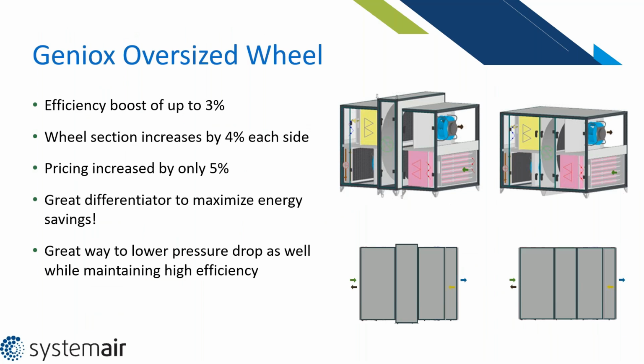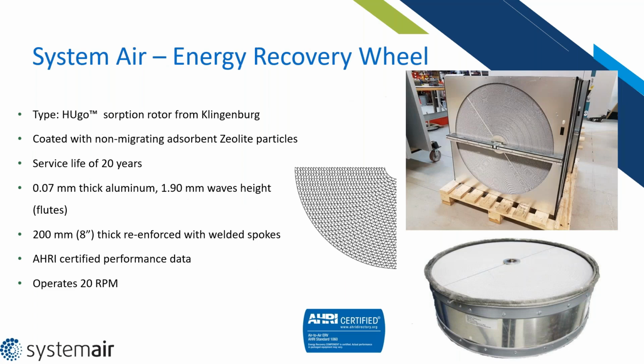Another cool option from Geniox is the oversized wheel. Instead of needing to boost that energy recovery by increasing the size of the whole cabinet, you can just increase the size of the wheel itself. This gives you an energy and efficiency boost of 3%. It's only about 4% bigger on each side, and you only really take a hit with a pricing increase of about 5%. So it's a good differentiator to maximize energy recovery savings, and a good way to lower pressure drop as well.